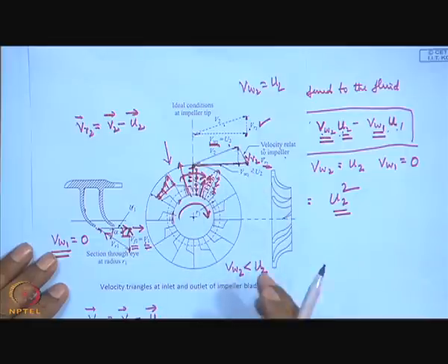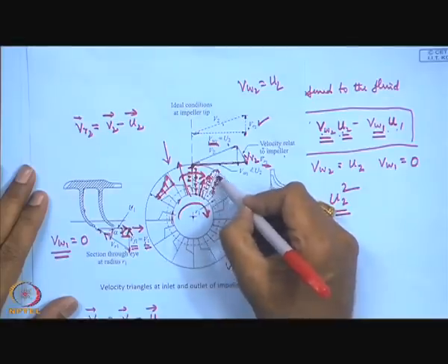It is the similar thing that happened in the case of the centrifugal pump. So, this is the slip, but you have to know the fluid mechanical principle of slip. It is because of the blade curvature and the rotation of the blade, the motion is being imparted to the fluid. At the same time, the fluid flows past the blade on the two sides of the blade, the leading edge and the trailing edge, which creates a sort of circulation combined with a linear flow in the radial direction, which creates this type of difference in pressure and a local recirculatory flow.